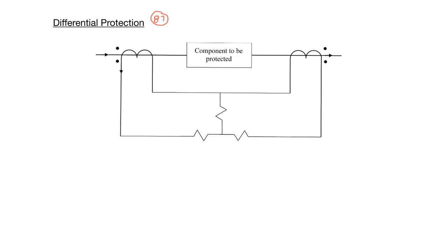Differential protection is basically looking at the current entering a device, I_in, and looking at the current coming out of the device, I_out. If the two currents are not equal, that means that there must be a fault in the protected component.